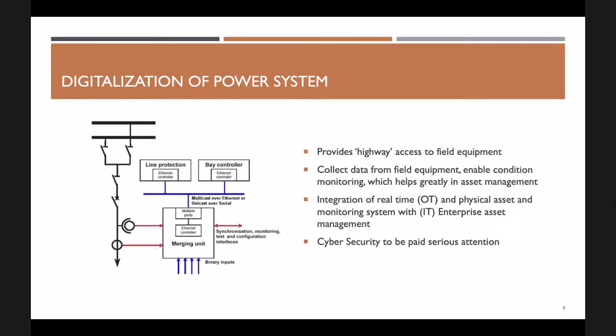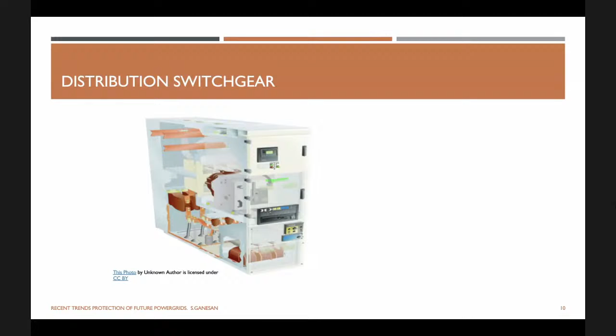So this is what we call a digital substation, in short. This is on the substation side. On the switchgear side, it has already happened. Most of the current transformers and voltage transformers are of the latest technology, with digital outputs directly connected to the IEDs. You don't find any more conventional switchgear lamps or annunciators on the front. We possibly have a single IED on the front, and that's what you use for interfacing with the human.